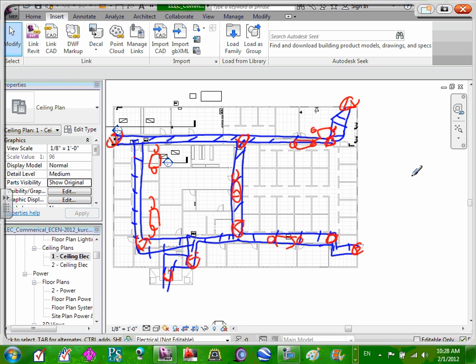And I think, Nick, even if the circuit breaker that feeds the classroom is off, if somebody turns the circuit breaker off in this room, that light will go on, right? Yes. They have a sensing mechanism. That's what we're going to be doing on the next project too, putting that little relay with an emergency panel backed up by generator. But I thought, since this is the first time we've ever done bug eyes in the project, it would be really nice to introduce them. They're commonly used out there because they're cheap mainly. They're a lot cheaper than a generator to maintain and meet the code.